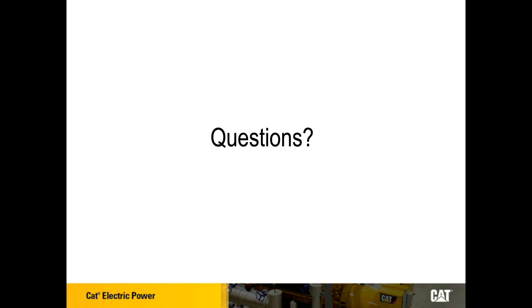Yeah, Jeff, that's a question we get pretty often. Dual fuel, sometimes referred to as bi-fuel, is when you add or fumigate natural gas in the intake system of a diesel generator, and it basically just displaces some of the diesel burn. Caterpillar actually offers bi-fuel generators and kits to make existing generators bi-fuel, meaning diesel and natural gas, but those are generally applied outside the U.S. The challenge we have in the U.S. is that the EPA hasn't recognized bi-fuel in their standards yet, so that's generally an outside the U.S. solution.